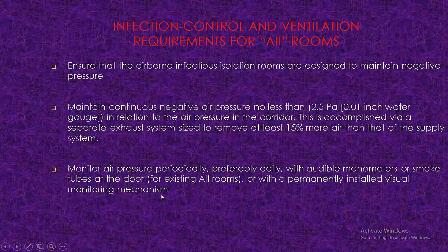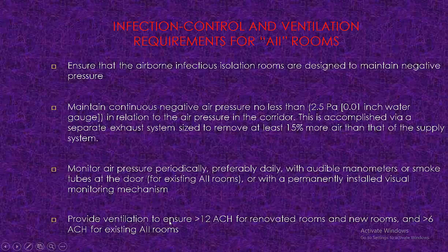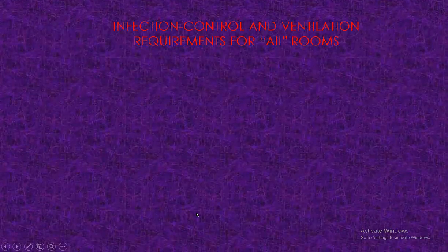monitoring mechanism. So provide ventilation to ensure greater than 12 air changes per hour. So we can provide ventilation that ensures 12 air changes per hour are required for renovated rooms and new rooms, and greater than 6 air changes are required for existing AII rooms.